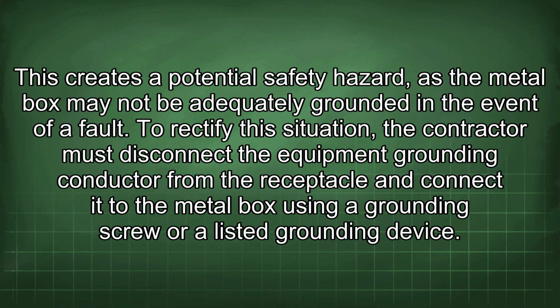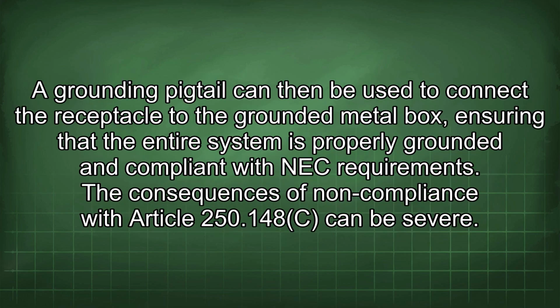This creates a potential safety hazard, as the metal box may not be adequately grounded in the event of a fault. To rectify this situation, the contractor must disconnect the equipment grounding conductor from the receptacle and connect it to the metal box using a grounding screw or a listed grounding device. A grounding pigtail can then be used to connect the receptacle to the grounded metal box, ensuring that the entire system is properly grounded and compliant with NEC requirements.